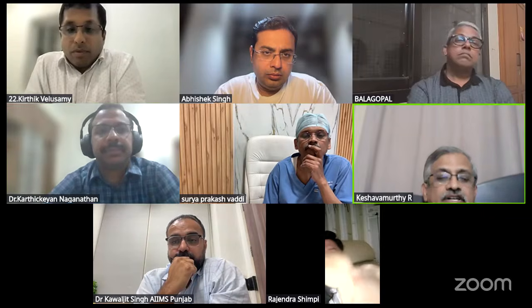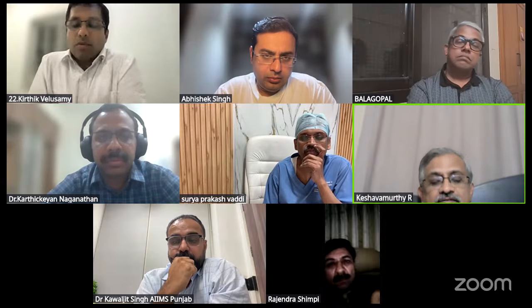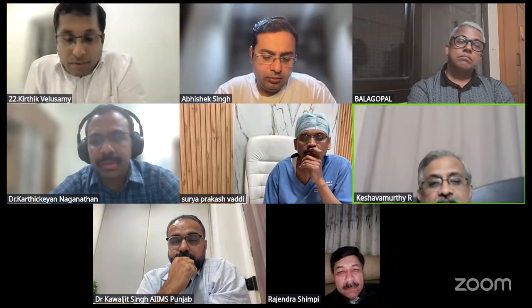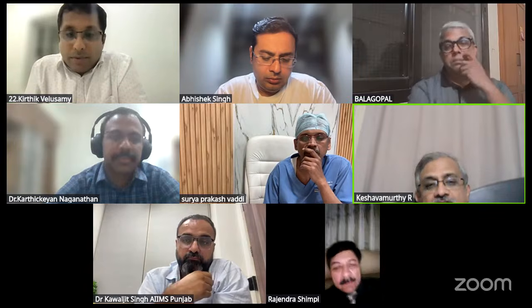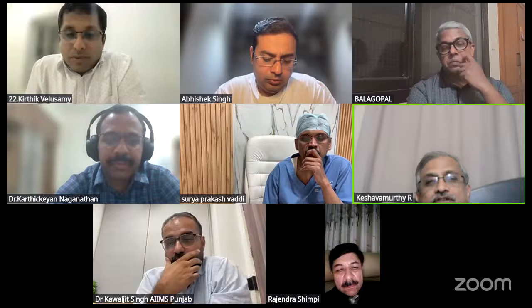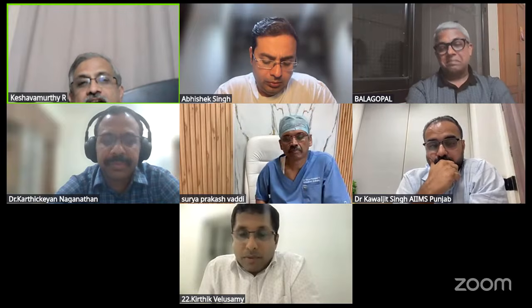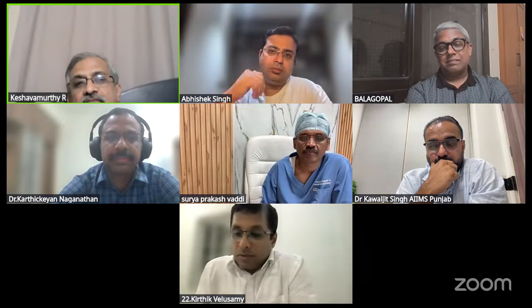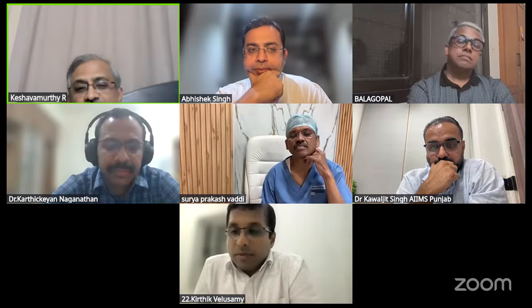Yeah, Keshav, sir? The important thing in high level disinfection, when you're using Cidex, when you do pre-cleaning, you have to dry the instruments before you immerse them again. If you keep the wet instrument in again, it's not going to be good for disinfection. So it's important that you dry the equipment and then immerse it in Cidex again. Very valid point, sir. Generally people don't do that. They just wash, rinse it, and then put it into Cidex.